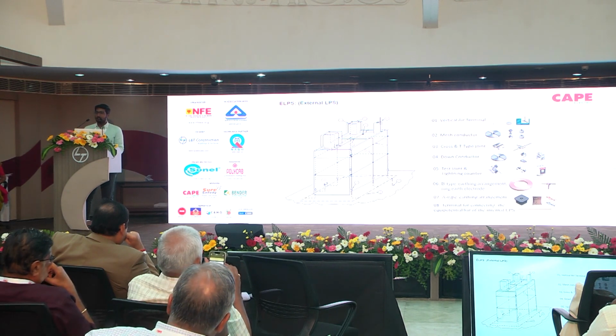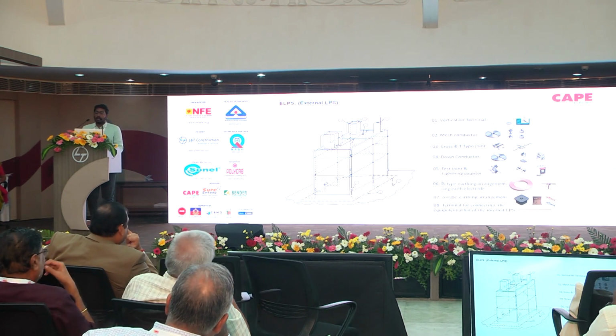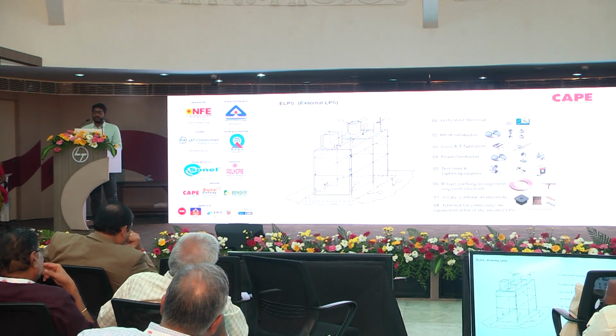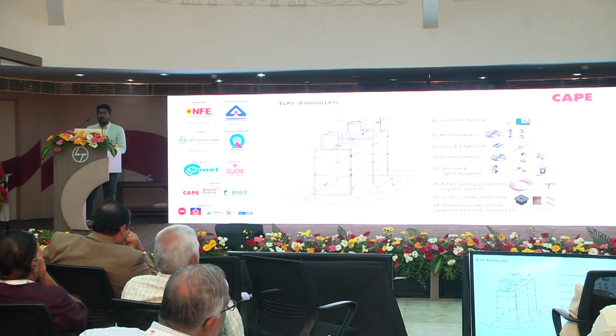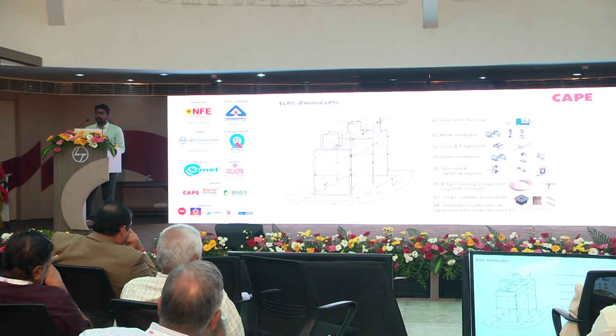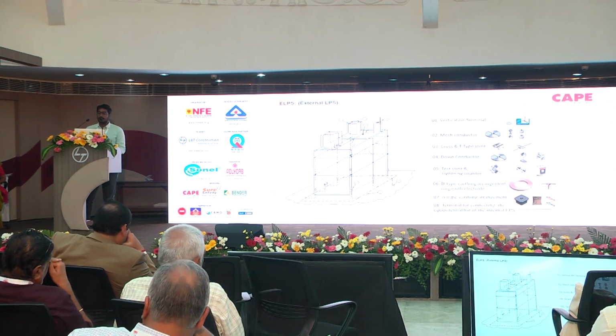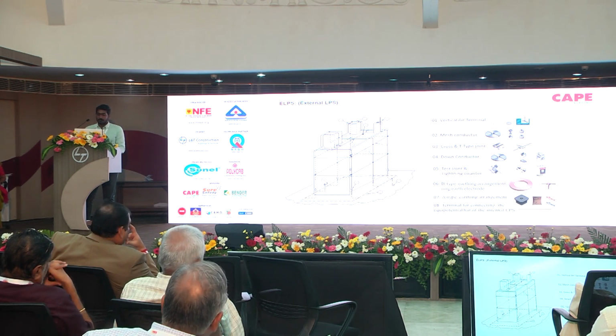So the first one is the vertical air terminal, which is nothing but a rod placed over the terrace or in the flat terrace area in order to protect the MEP equipment as well as projected AC ducts, such kind of things. So there are different models subject to that. There will be wall clamp provisions, or a stone-based provision, or if a metal sheet is there, based on the profile of the sheet, the vertical air terminal stands and clamping accessories will be designed.